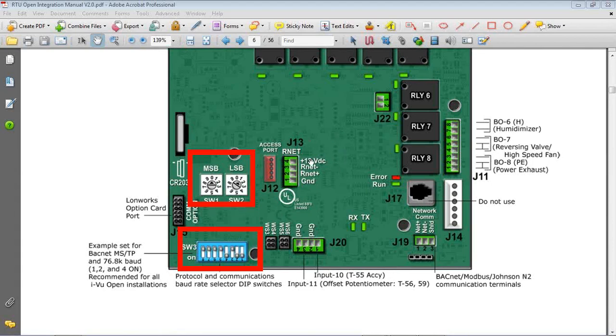So locally, in order to communicate, you have to first set each of these rotary switches to the address you want for each card. If you have the same address on two cards wired together, you're not going to be able to communicate. You're going to run into big issues. So each controller has to have an individual address.